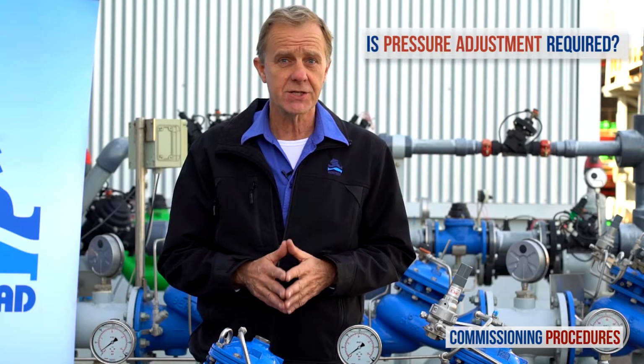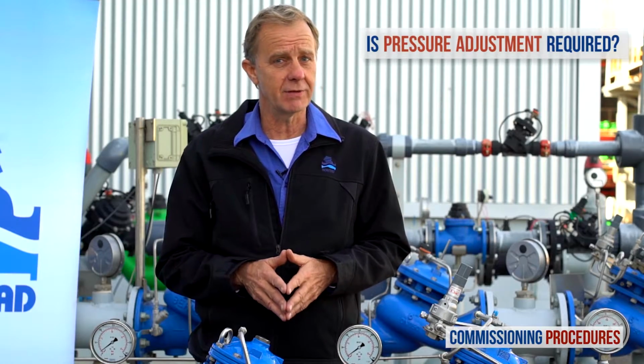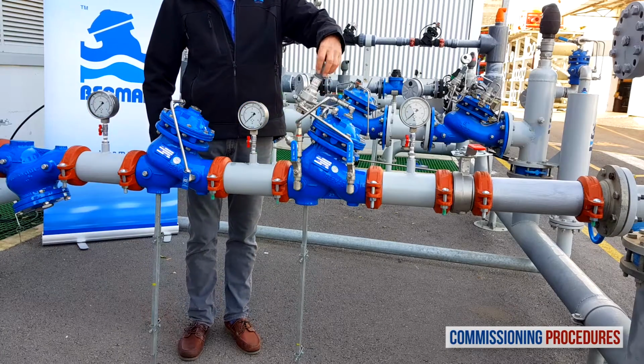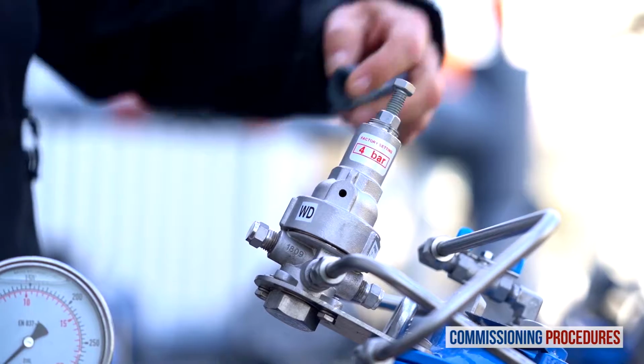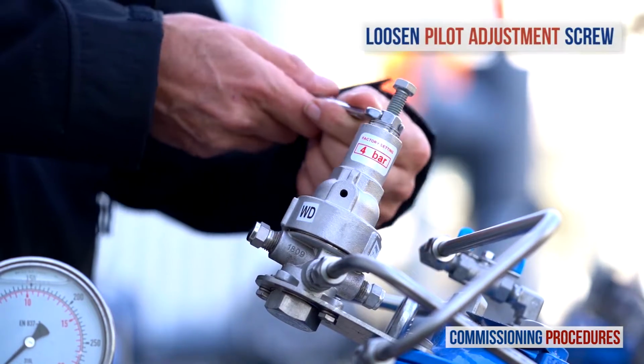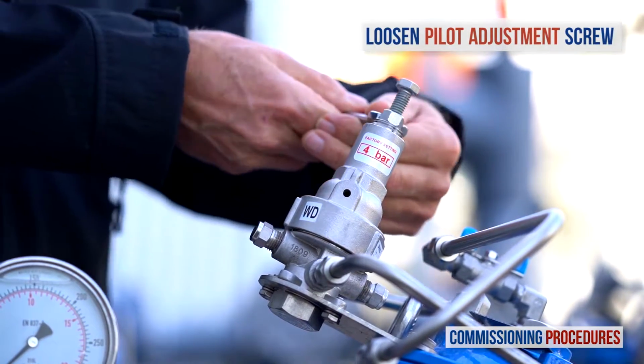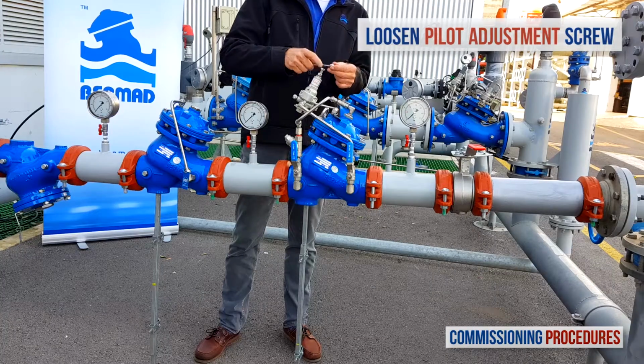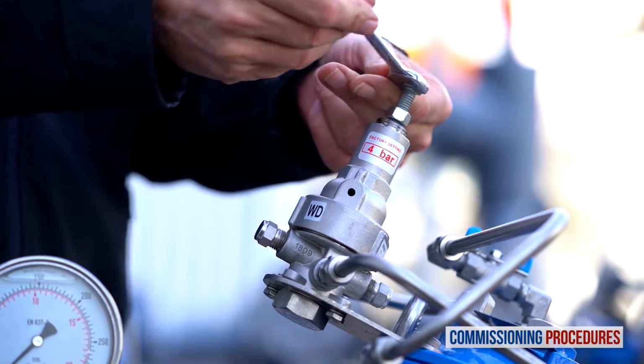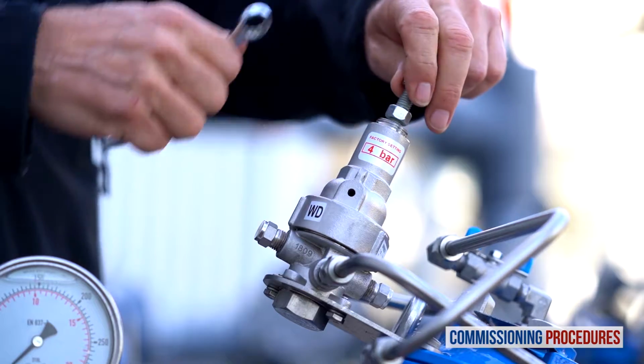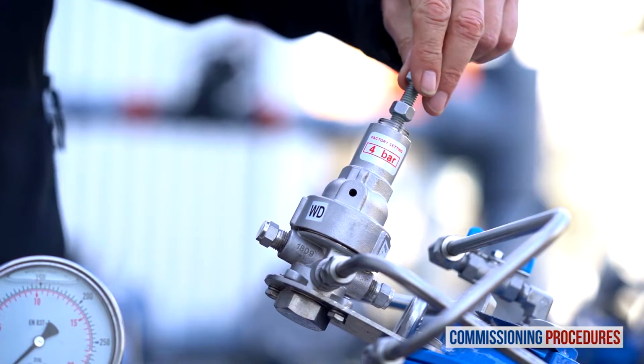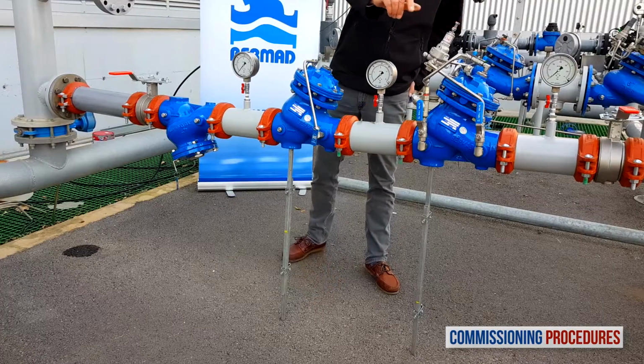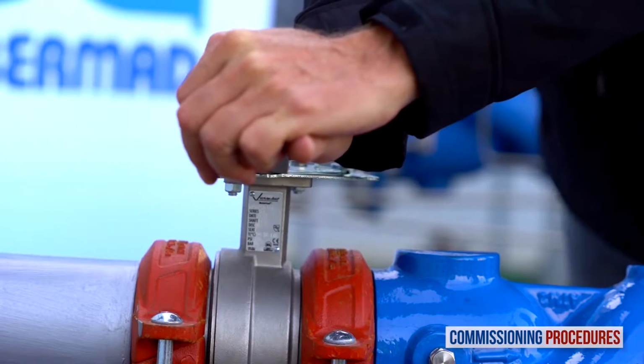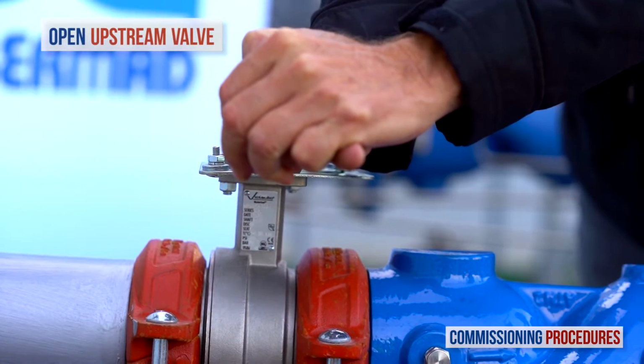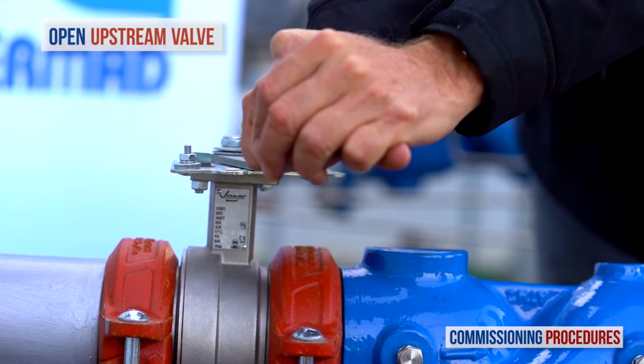If this is not the case, you'll need to adjust the pilot to the required level. To adjust the pilot, all you need to do at this point is to prepare for it by completely unscrewing the pilot's adjustment screw until it becomes loose. This will cause the secondary valve to close when water is introduced, allowing us to recalibrate from zero pressure to the required value. All right, now slowly, fully open the upstream isolating valve to fill the station with water.